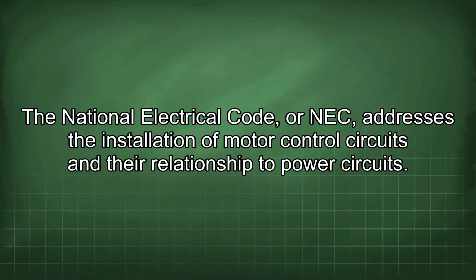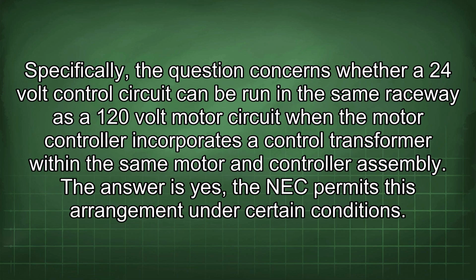The National Electrical Code, or NEC, addresses the installation of motor control circuits and their relationship to power circuits. Specifically, the question concerns whether a 24-volt control circuit can be run in the same raceway as a 120-volt motor circuit when the motor controller incorporates a control transformer within the same motor and controller assembly. The answer is yes, the NEC permits this arrangement under certain conditions.